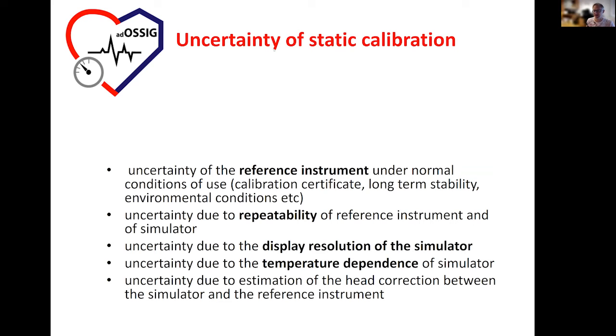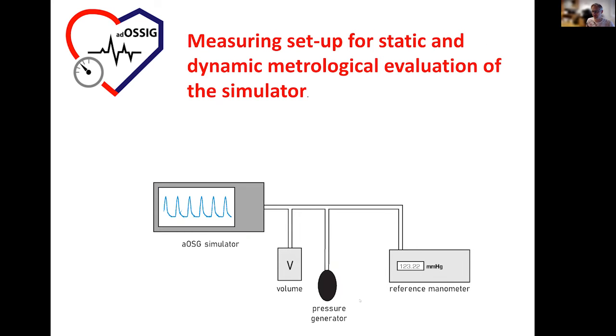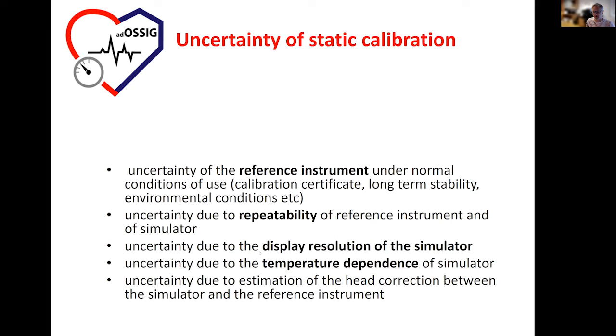The uncertainties, or the uncertainty budget, meaning the detective work, what are all the quantities which can influence such a static calibration, are written here. There are also others, of course, but the major ones are written here. Like the uncertainty of the reference instrument, the repeatability of both the simulator and the reference manometers, and then some errors which come from the pressure generators, from all the tubing, the leakage, also some environmental conditions like temperature dependence, also humidity dependence, and so on.